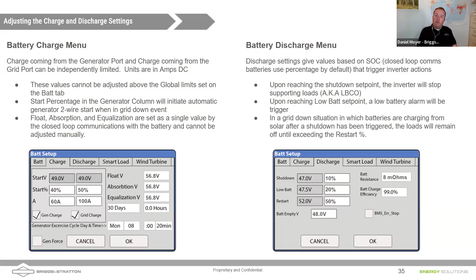That's a great point. We don't want to do a black start, where the battery is completely drained and turns itself off to protect itself, leaving the inverter totally dead. When the grid comes back, the inverter restarts, but we also want to be able to get solar on the next day. A parasitic draw on a Sol-Ark might be 50 to 100 watts, which could be 1.2 to almost 2 kilowatt-hours a day. That draw can vary, but it's a good point that with a bigger battery, you can set that threshold a little lower.